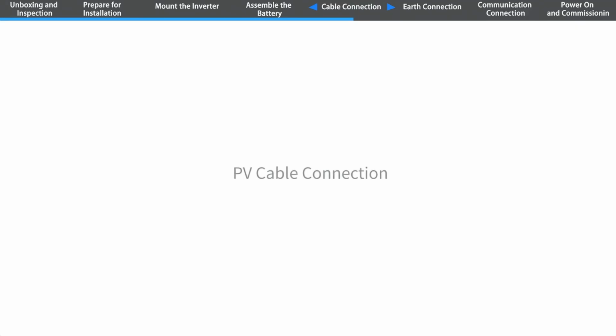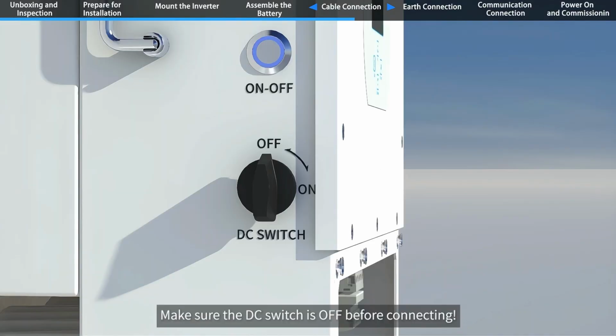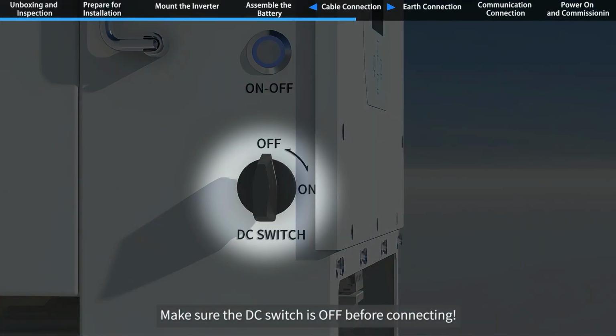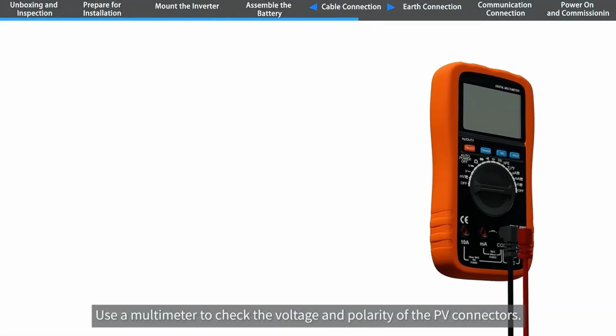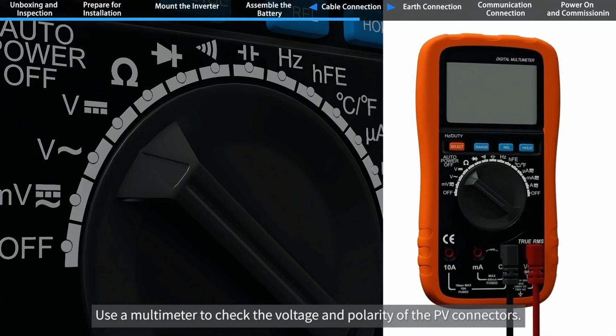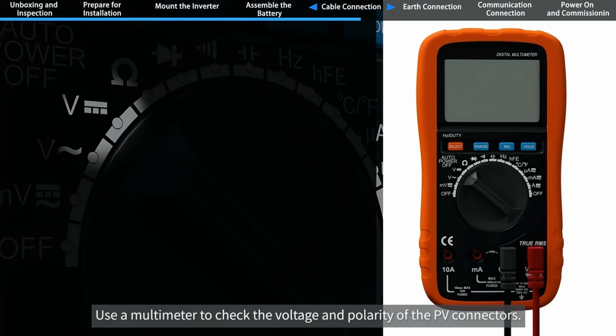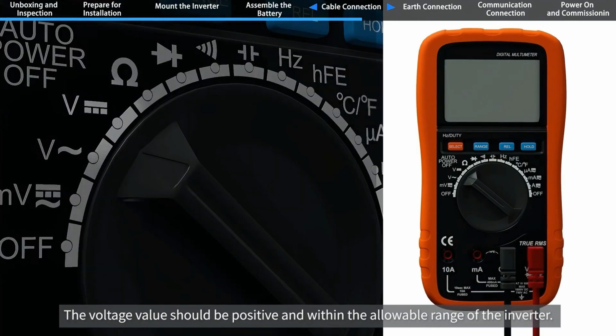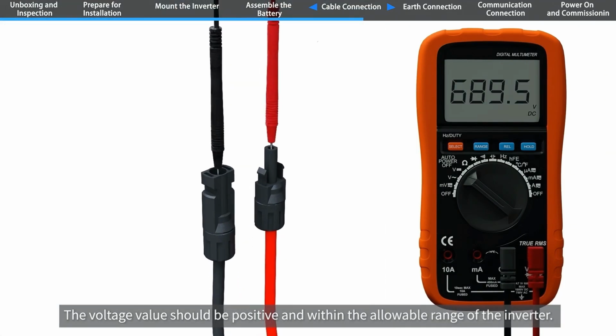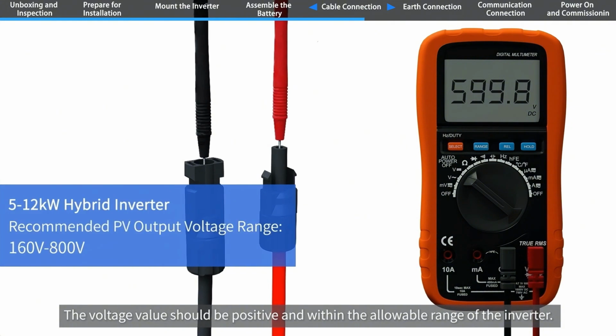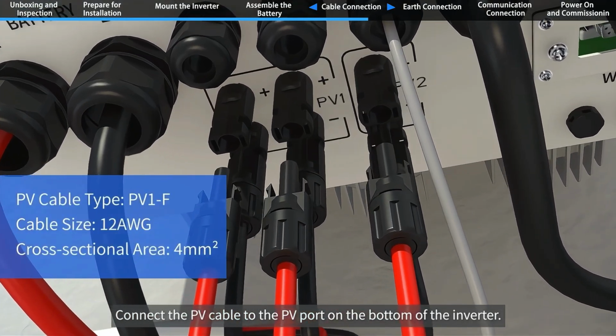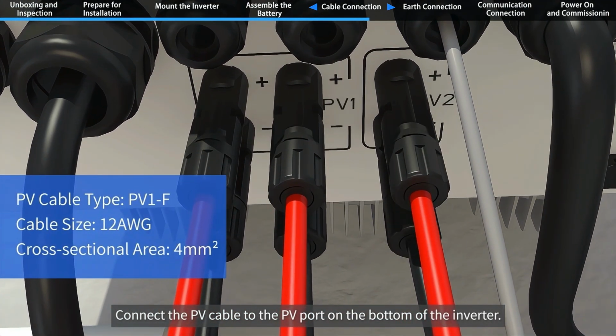PV cable connection. Make sure the DC switch is OFF before connecting. Use a multimeter to check the voltage and polarity of the PV connectors. The voltage value should be positive and within the allowable range of the inverter. Connect the PV cable to the PV port on the bottom of the inverter.